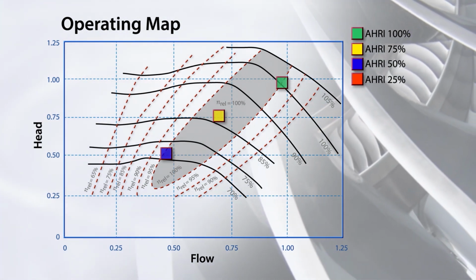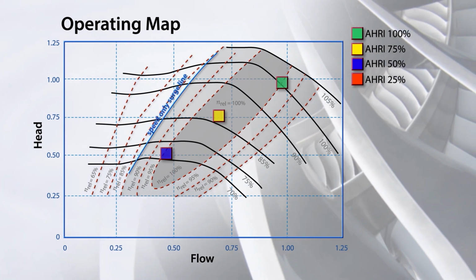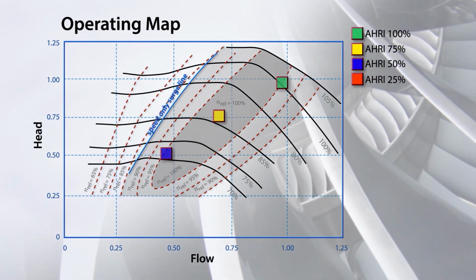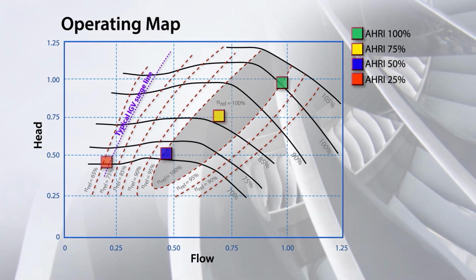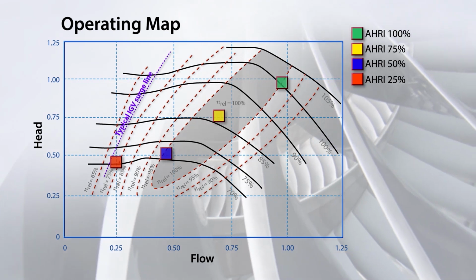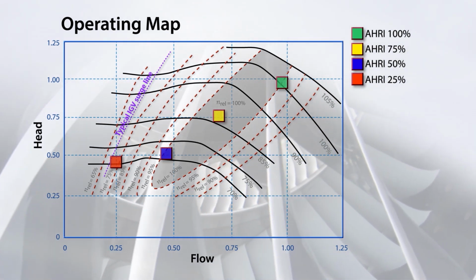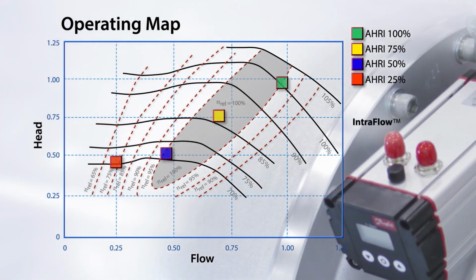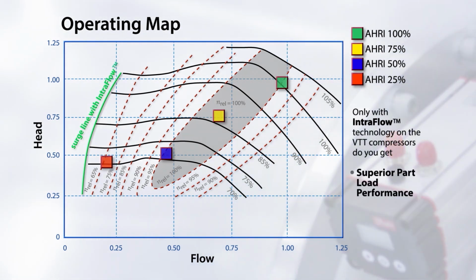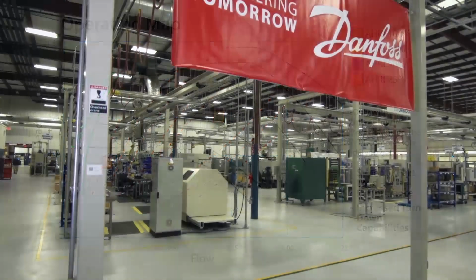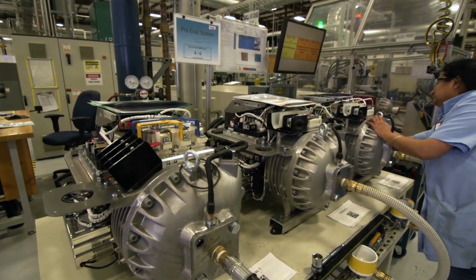Conventional use of variable inlet guide vanes, IGV, increases the operating envelope versus speed-only designs, but may not address other possible operating conditions. In some cases, the IGV operating point extends into the surge zone, requiring operation at higher speeds, resulting in excess capacity, compressor cycling, and higher power. The introduction of IntraFlow, or IFV, technology extends the stable operating range, resulting in a larger envelope capable of handling more off-condition points while also delivering increased efficiency. Superior part load performance and a larger operating envelope without using IGVs or variable geometry diffusers can only be achieved with IntraFlow technology. Danfoss continues to deliver innovative solutions for the HVAC industry.